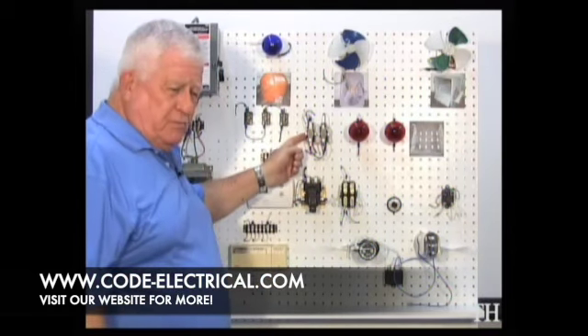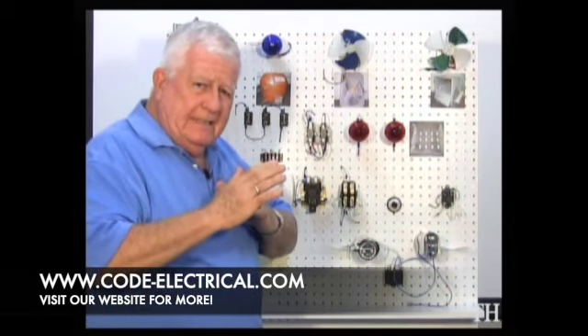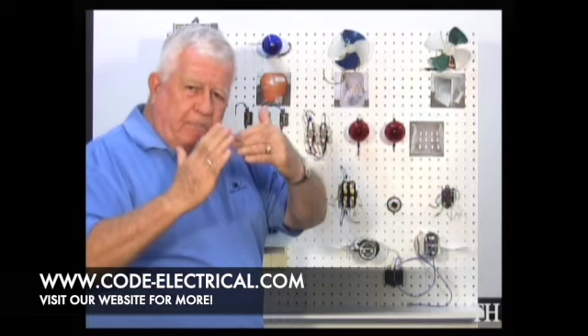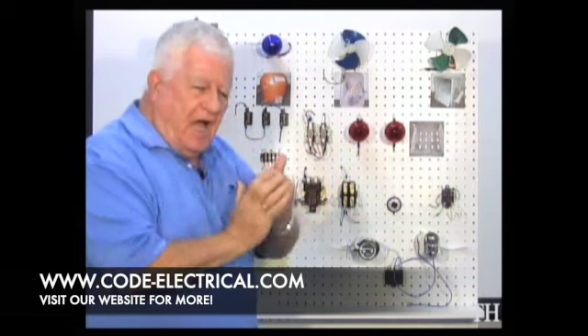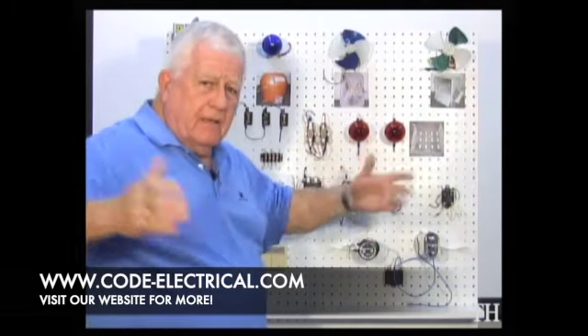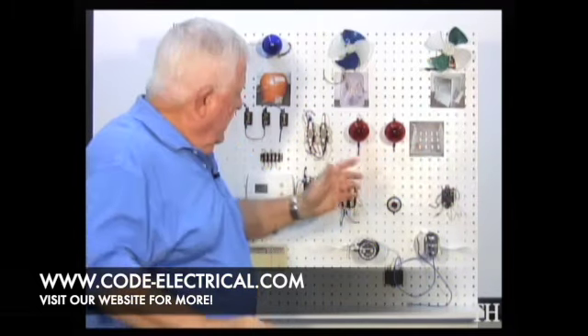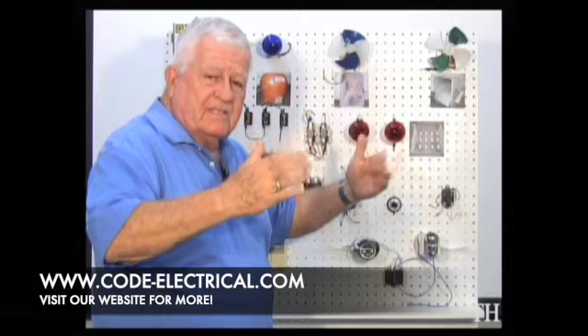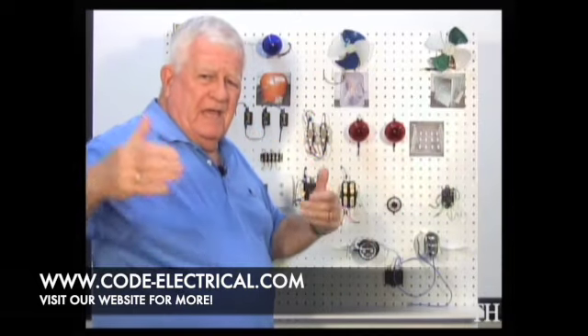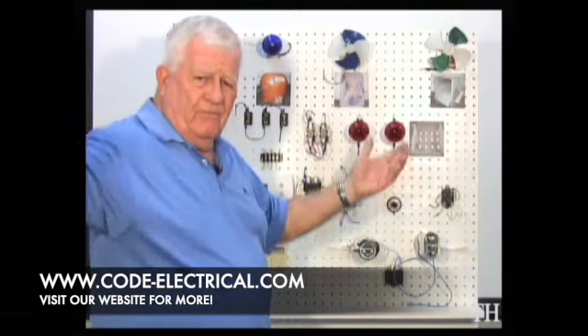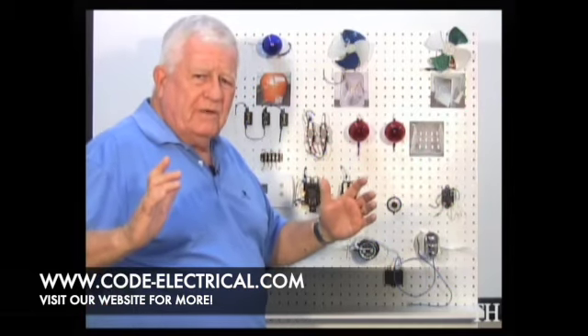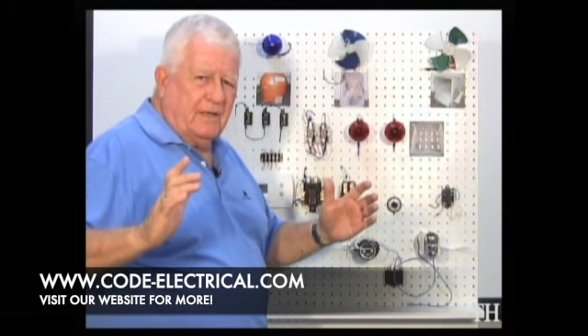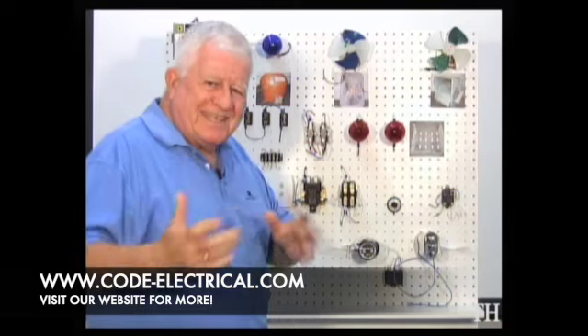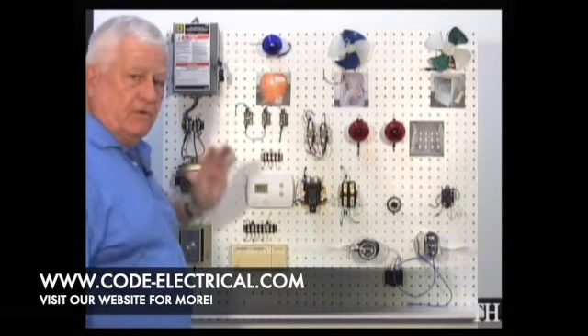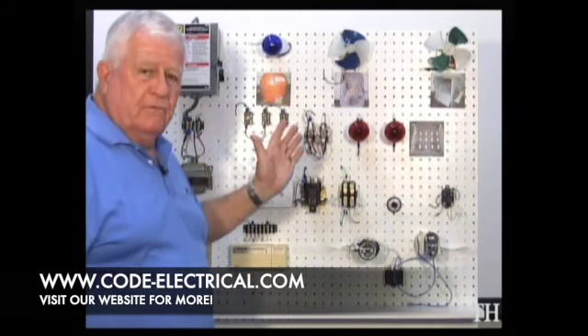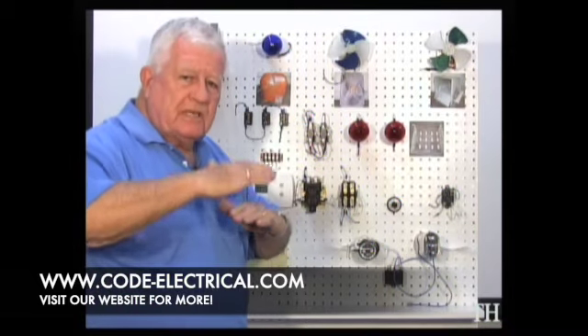On this warp switch, when we heat it, it's going to expand and make contact. When it makes contact, it sends a signal like 'give me some heat.' You'll have another one bring in a second layer of heat, or in an industrial setting you may have 3, 4, or 5 of these strips. You don't want them all at once, because too much current drawn instantaneously can trip the breaker or blow the fuse. So we bring them in a sequence.